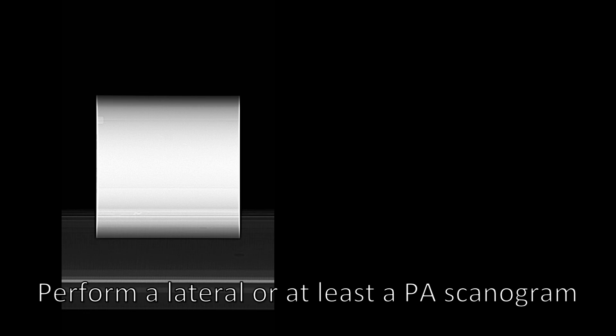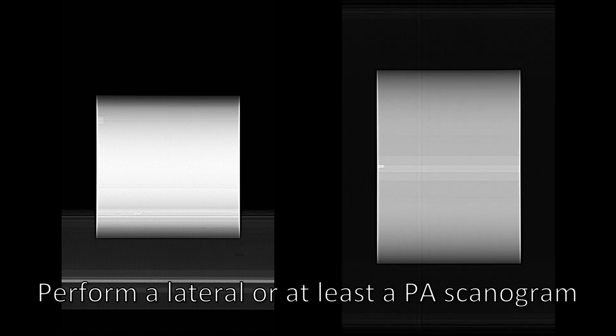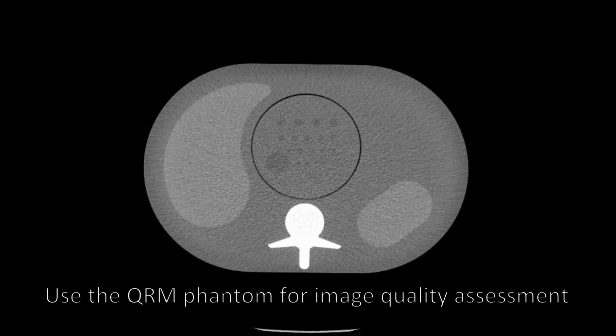Perform a lateral or at least a posterior anterior scanogram. Use the QRM phantom for image quality assessment.